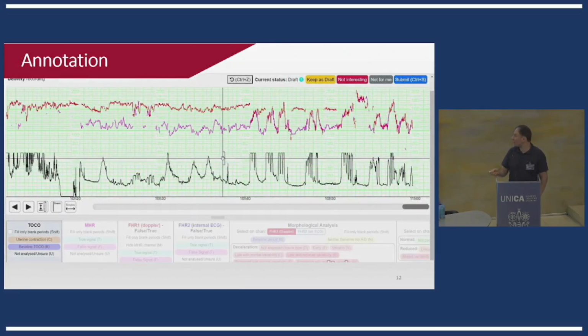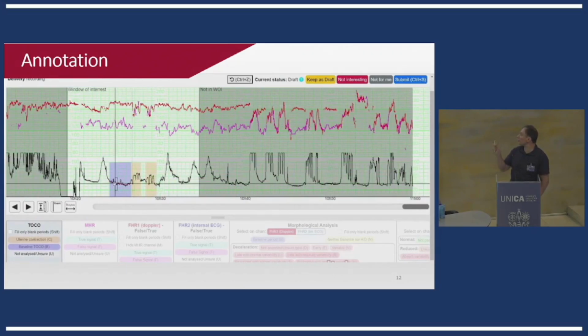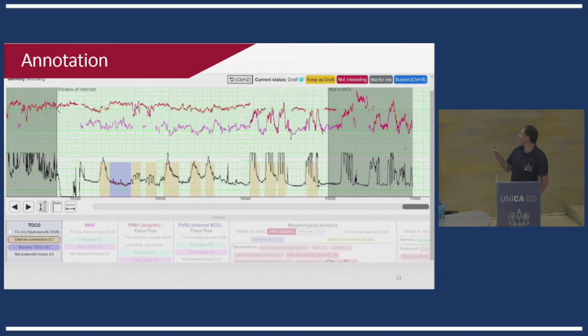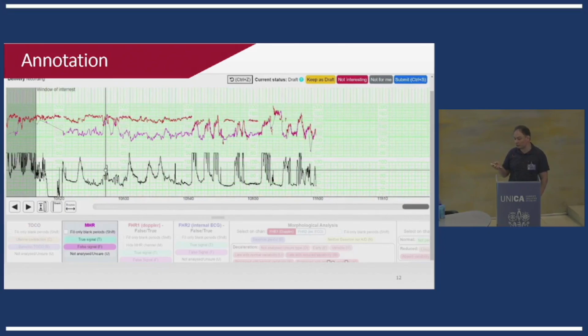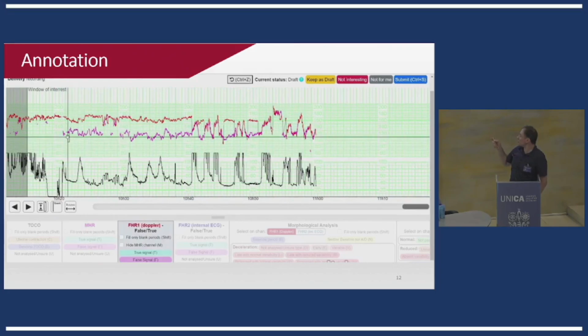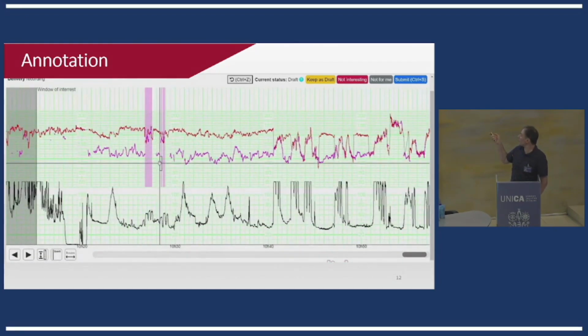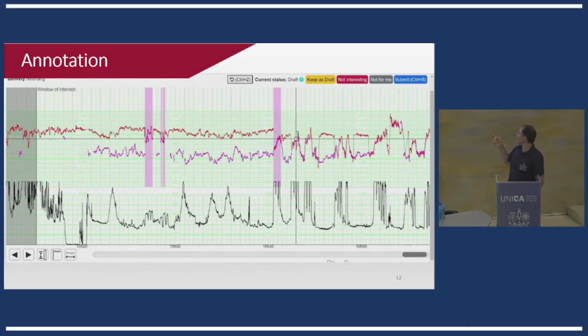This is an example of the annotation process sped up 3 times. You click on the beginning and end of each contraction first. Then you fill the period, saying which is baseline, TOCO. Here you analyze the violet channel, the maternal heart rate channel, just to say it's always 2 signals. Here on the fetal heart rate, we recognize some maternal interference, so the expert analyzes it.